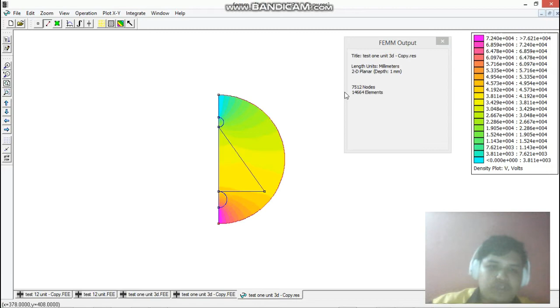Then we also make the simulation for contamination condition. By changing the insulator, we add the contamination on the insulator and change the surrounding to contamination condition. The value of the contamination permittivity is 80.